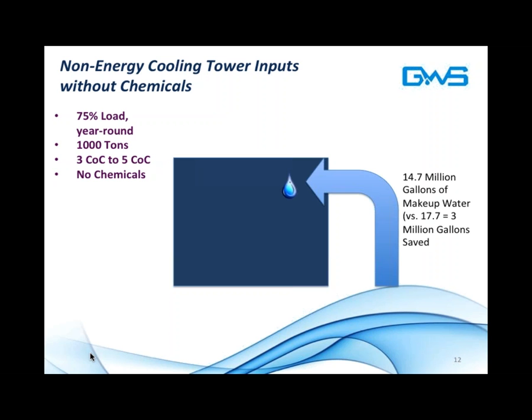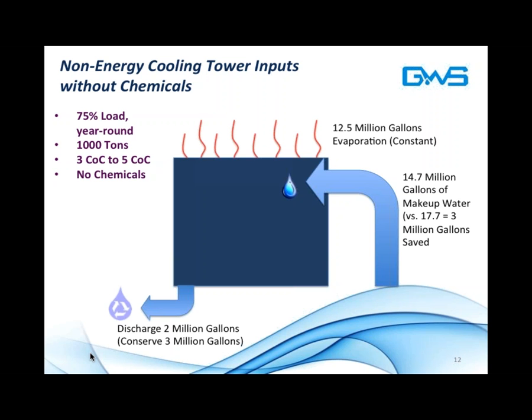A tower like this, same tower, but running now at 5 cycles of concentration, with the assumption that no chemical inputs are required, will consume 3 million fewer gallons of water per year, or 14.7 million gallons of makeup water. Evaporation is constant, again, so you have 12.5 million gallons evaporated. And you're going to discharge roughly 2 million gallons, which is equivalent to saving approximately 3 million gallons of water. Without chemical inputs, that's just slightly harder water. And that water can be used on site, or at least dumped over to storm drain without incurring any sewer costs. This equates to more than 25% of water conserved in the system.